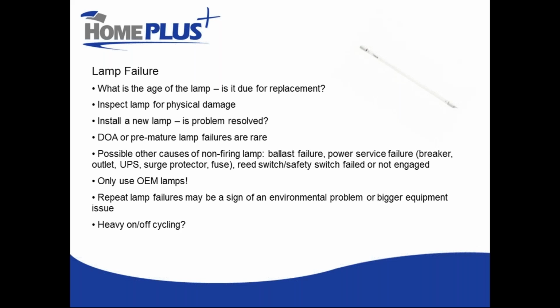I talked about being prepared. Part of being prepared is to have a spare lamp on hand. If you replace the lamp, does the problem go away? Especially if your system's telling you you have a failed lamp as opposed to an intensity problem, it's a pretty good chance you actually do have a failed lamp. Listen to what your system is telling you and use that spare to test and diagnose whether or not that's correct.